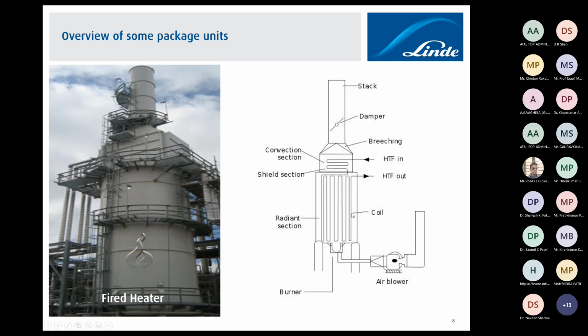So a fired heater is, you can say, a modified version of the boiler, where you can also see an air fan and burners at the bottom. A stoichiometric mixture is introduced here to produce the fire, and the first zone, where the temperature is the highest, is the radiation zone, and maximum heat is recovered here. The second zone is the convection zone, and there is some shielding section. The shielding section also gets some radiation heat as well as heat from the secondary heat in the convection zone. So basically the fluid first enters the convection zone, and then via the radiation zone it comes out at the desired delta T temperature, typically in the range of 150 to sometimes even as high as 300 degrees.